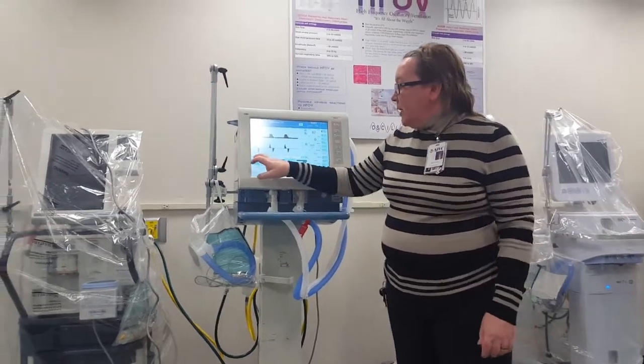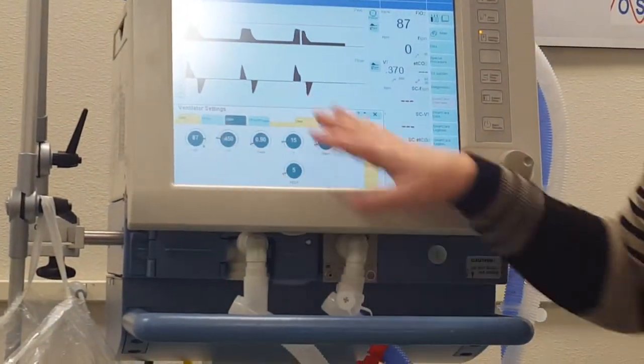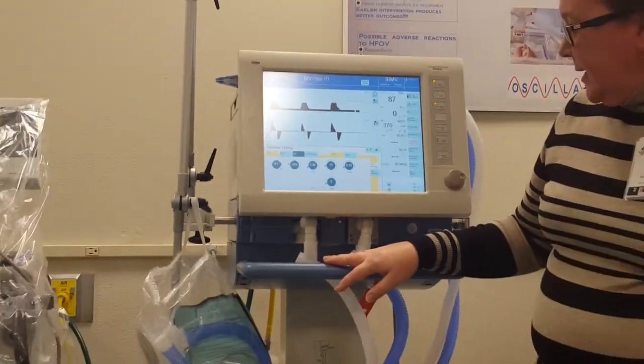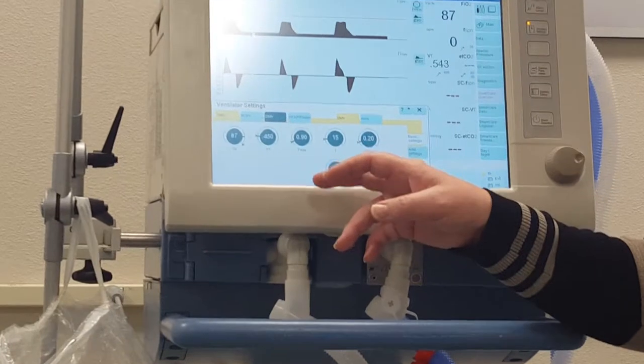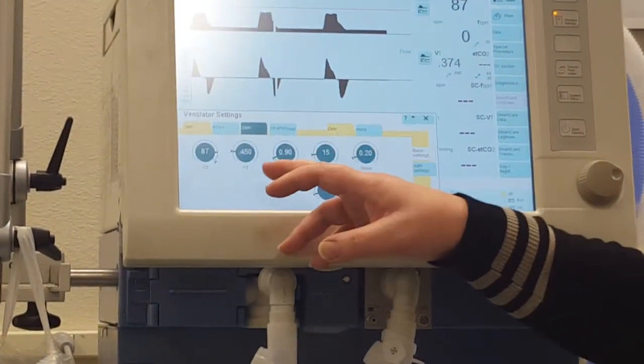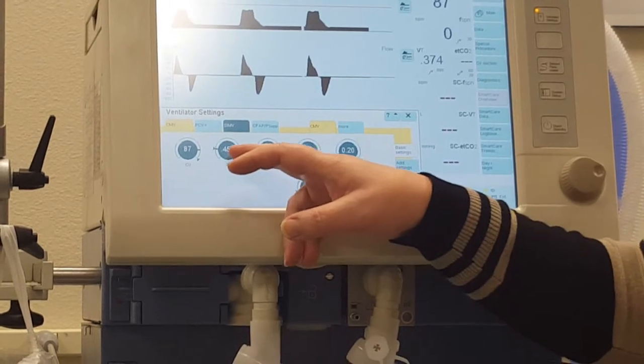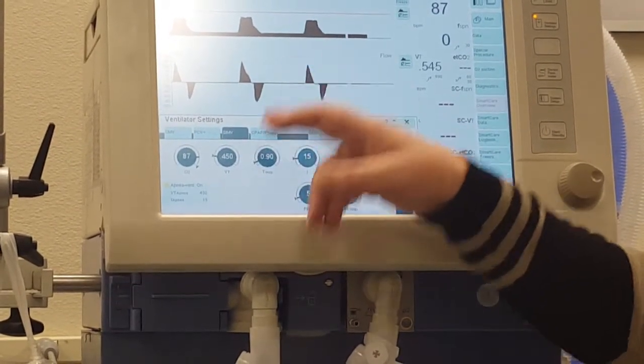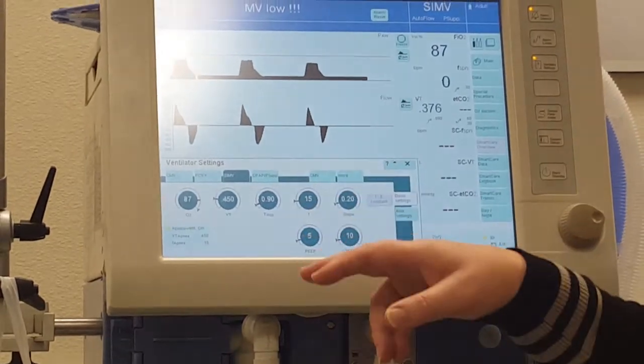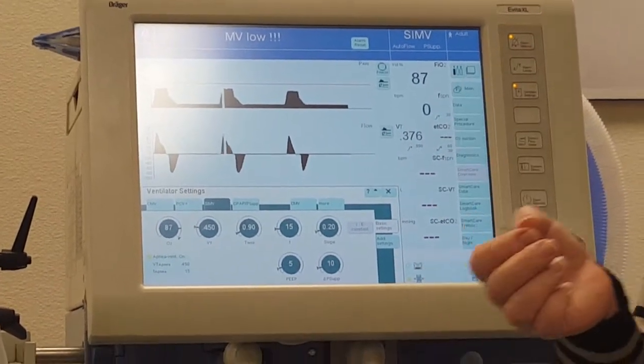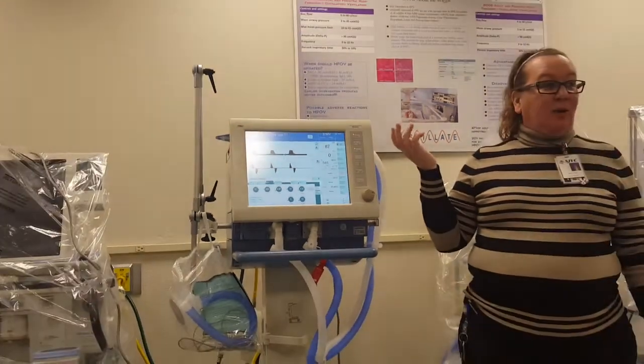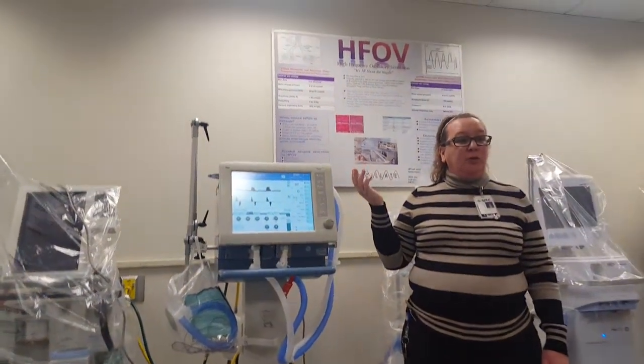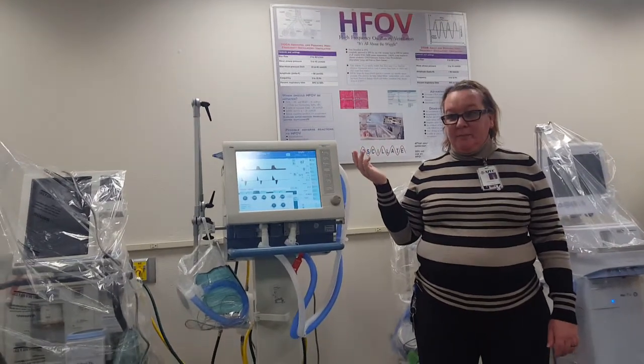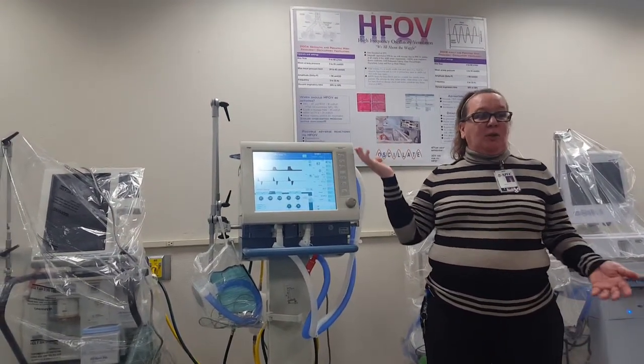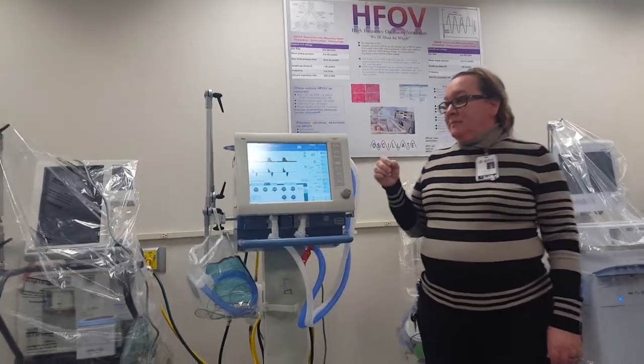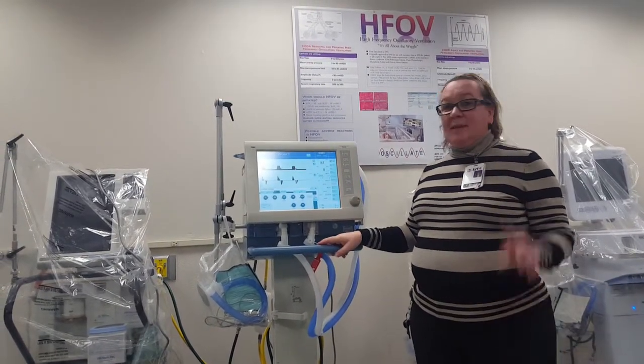And then depending on what mode you're in will depend on actually what settings you can set. Oh, the other thing that's unique to the DRAGER, because it's from Germany, your units are in actual liters, and so instead of your tidal volume being 450 cc's, it's 0.450 liters. That's very important when it comes to your alarm settings, because I'll see people put my alarm at like 1.20 because they think it's supposed to be 120, but that's really 1.2 liters, which would be huge. So it would have to be 0.12, exactly. You want the decimal point in front of it.